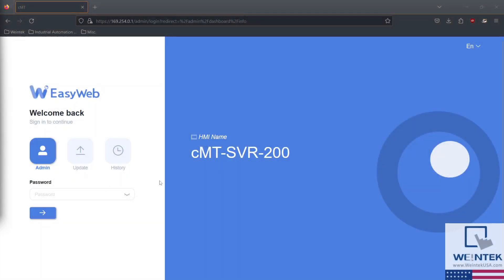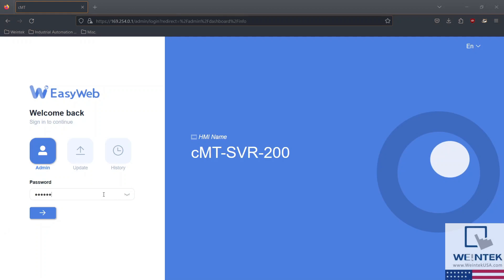Next up is the CMT SVR200. To view your EasyWeb dashboard, you'll need to enter the device's IP address into your browser's address bar. The default IP address for the Ethernet port is 169.254.0.1. Next, you'll be prompted to enter your device's password. 111111 is the default password for all Weintek HMIs.